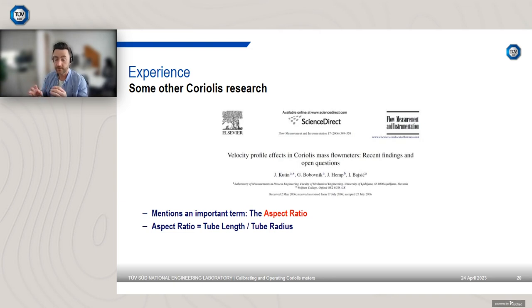So you have Coriolis meters, typically twin tube devices, so two tubes within the device. They all have different lengths depending on the manufacturer, the model, the meter size, and obviously a different tube radius again depending on those factors. So they all have different aspect ratios. I've not included the chart, but in one of my journal papers I've calculated the aspect ratios of some common Coriolis meters from the different manufacturers, depending on their meter size, and the aspect ratio does differ. This paper here found that the aspect ratio was strongly correlated with the effect of velocity profile effects.